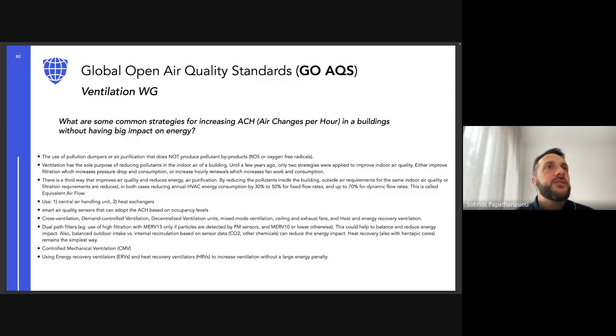Another common ventilation has the sole purpose of reducing pollutants in the indoor air of a building. Until a few years ago, only two strategies were applied to improve indoor air: either improve filtration, which increases pressure drop and consumption, or increase hourly renewals, which increase fan work and consumption. And finally, the use of pollution dampers or air purification that do not produce pollutant byproducts like radicals, oxygen-free radicals or ozone in some cases.